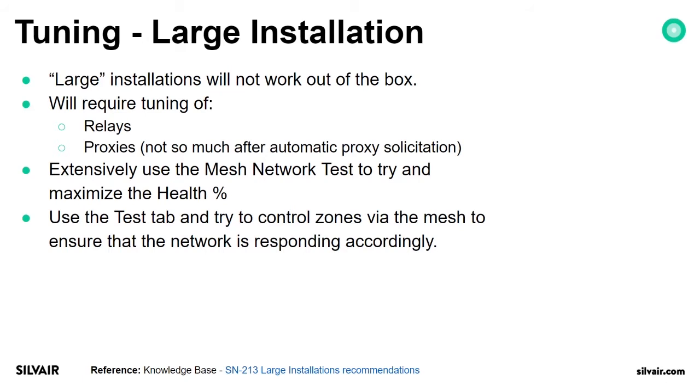So in large installations, to sum this up, I would say you do not always need 100% of mesh quality everywhere. If you have one floor with different control scenarios without a gateway, where you don't use any scheduling on a massive scale on the whole floor, maybe it's not so bad if some zones cannot communicate with 100% mesh quality.